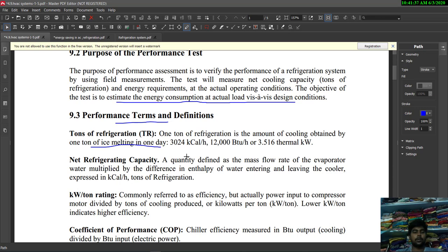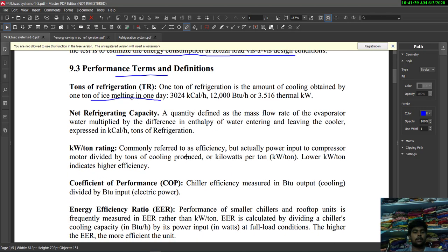Next is net refrigerating capacity — a quantity defined as the mass flow rate of the evaporator water multiplied by the difference in enthalpy of water entering and leaving the cooler. It is expressed in kilocalories per hour or tons of refrigeration.